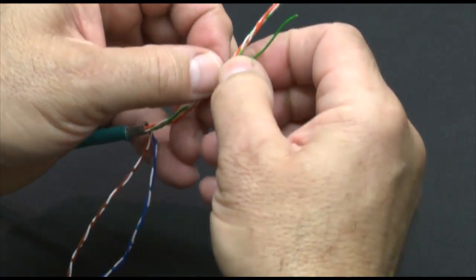Take the brown and white pair and blue and white pair and bend them down and out of the way. Separate the conductors and match them to the color coding on the small door of the connector. Orange stripe, orange solid, green stripe and green solid.